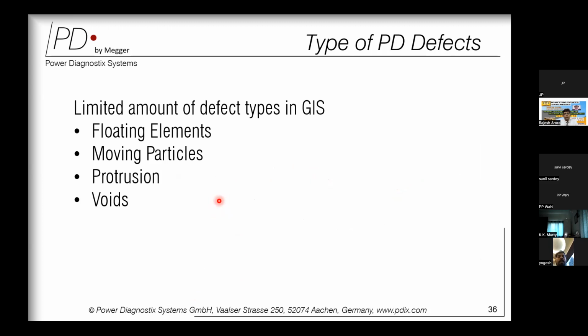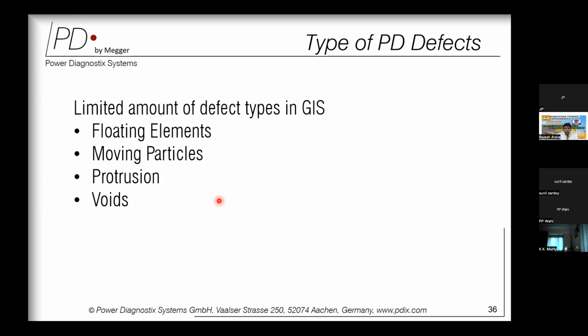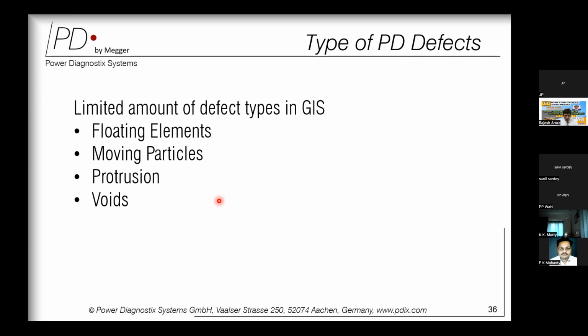So as we see, GIS partial discharge is relatively simple as compared to PD in a transformer, because you have a limited amount of defect types in terms of floating element, moving particle, protrusion or void. These are very common defects in partial discharge.